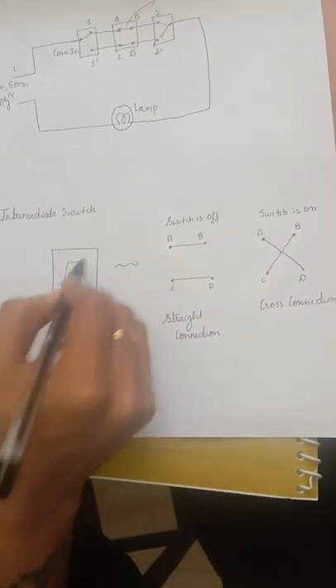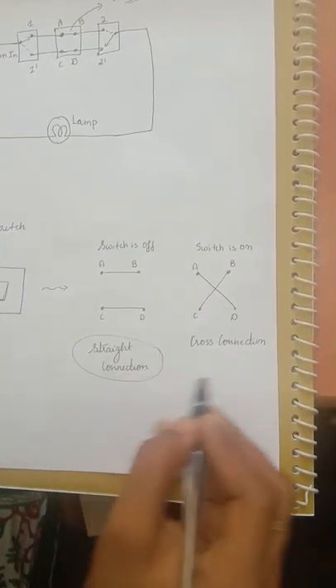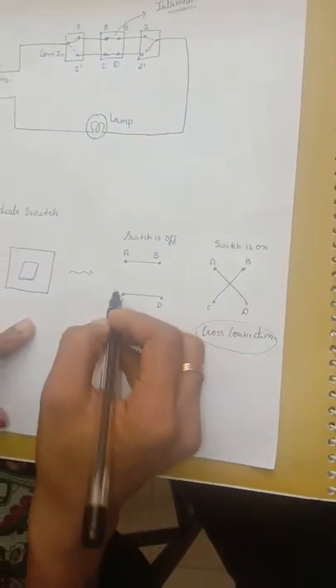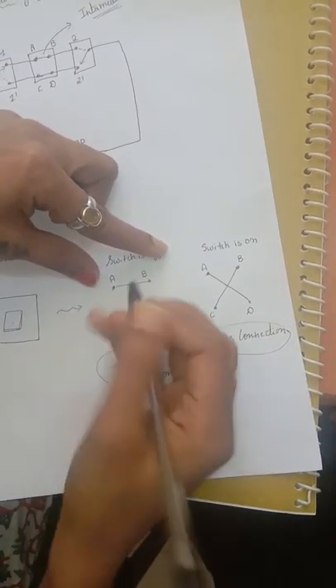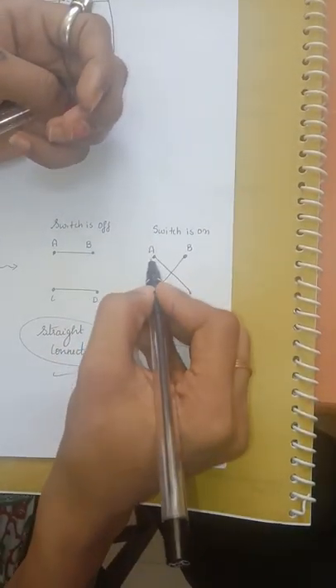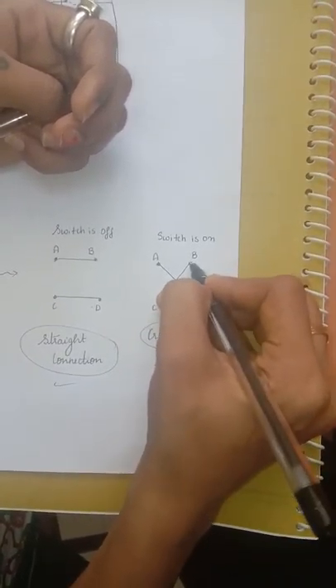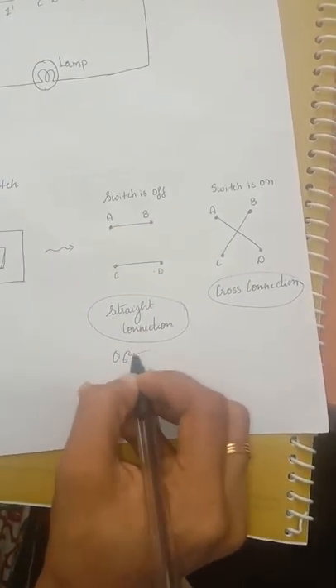The intermediate switch has four terminals: A, B, C, D. It has two combinations — a straight connection and a cross connection. Under the off condition (straight connection), terminal A is connected to terminal B and terminal C is connected to terminal D. When the intermediate switch is switched on (cross connection), the contacts get interchanged: A gets connected to D and C gets connected to B. This is how the intermediate switch operates under off and on conditions.